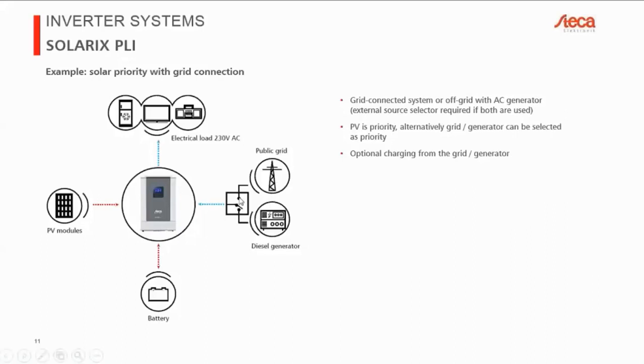Also, you don't need to worry too much about the switchover time here, because as soon as the inverter detects a loss during your switching, it will automatically switch over to the battery. And then once you have a stable AC voltage again on the AC input, it can then switch to that new source after, of course, it has synchronized to that source. So basically, the PLI takes away all the heavy lifting of switching quickly and of synchronization. You don't need to worry about that.